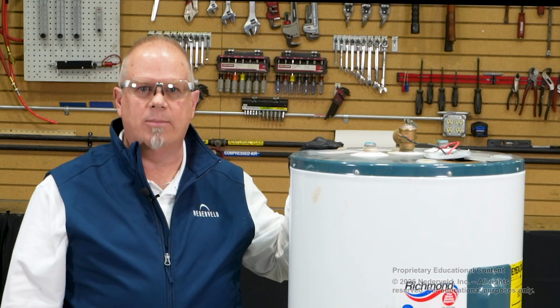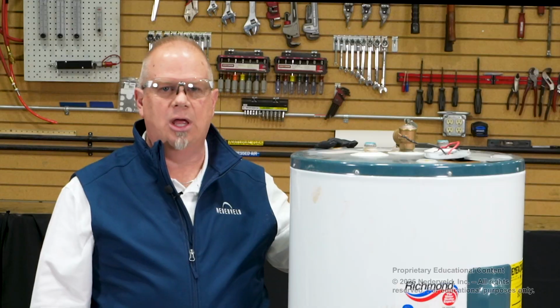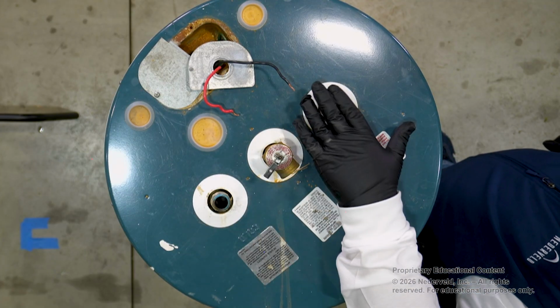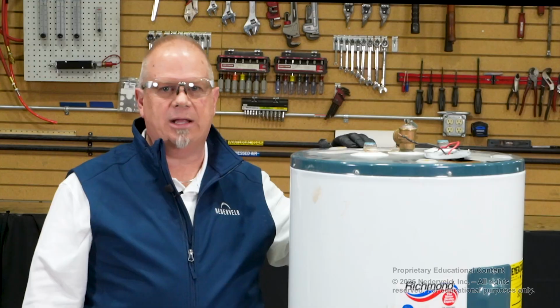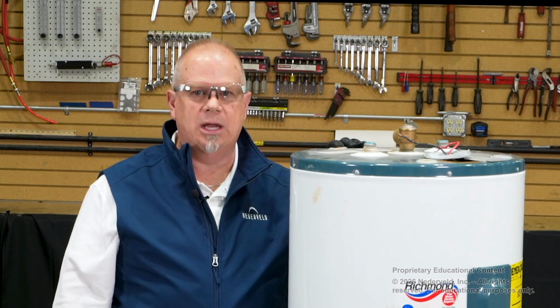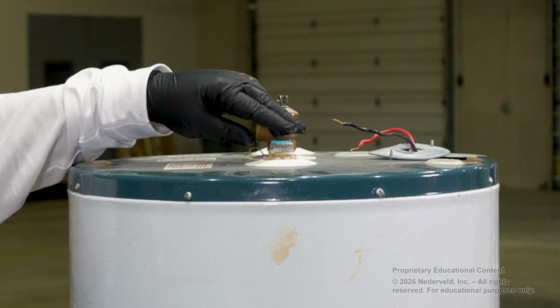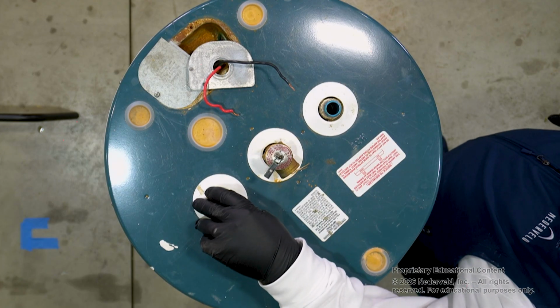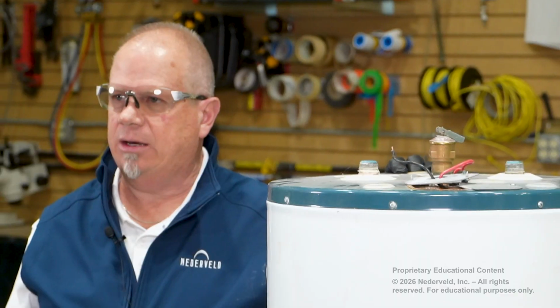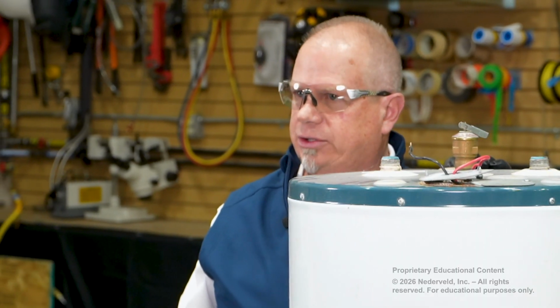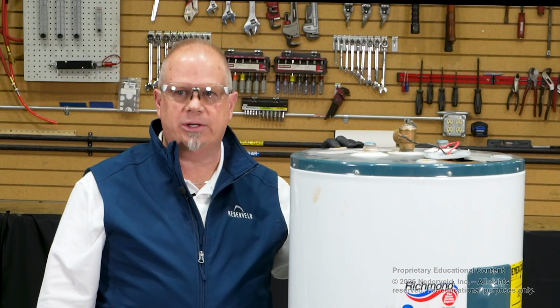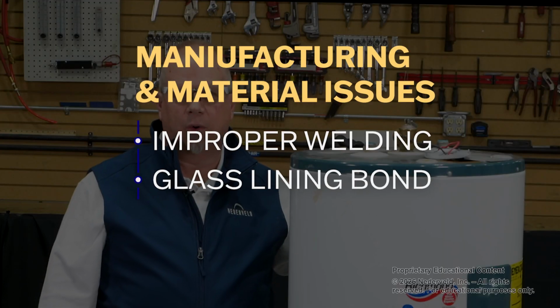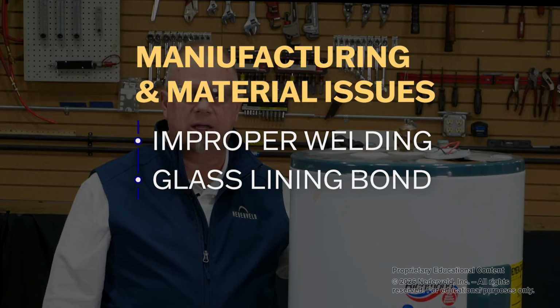Installation-related issues are mostly related to improper connection of the water connections. For instance, a polymer pipe connected directly to the inlet and outlet, and another one is a lack of a dielectric connection at these portions. A complicated installation issue is the lack of a pan or T&P piping. This is essentially the deletion of a required safety element of the water heater installation. Manufacturing and material issues such as improper weld or insufficient bonding of the glass lining do occur.